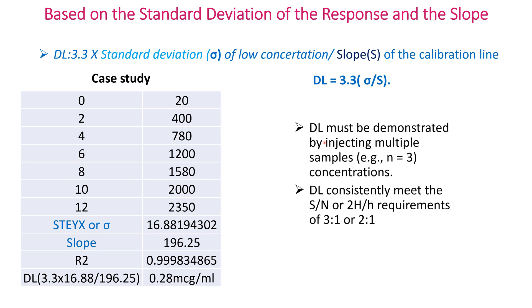DL must be demonstrated by injecting multiple injections — at least three. DL must consistently meet the S/N (2H/h) requirement of 3:1 or 2:1.